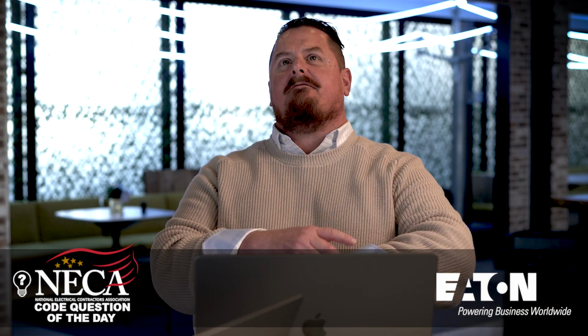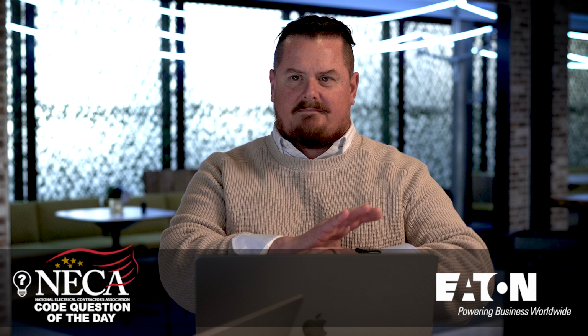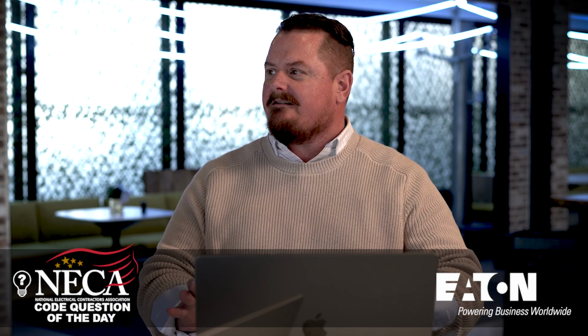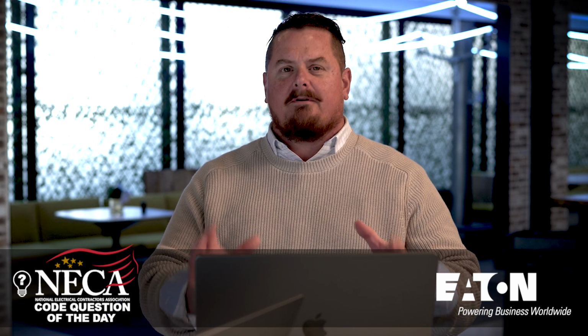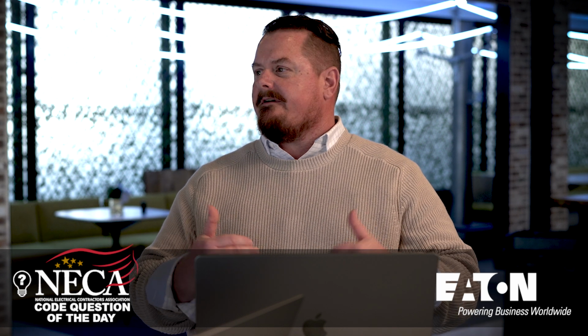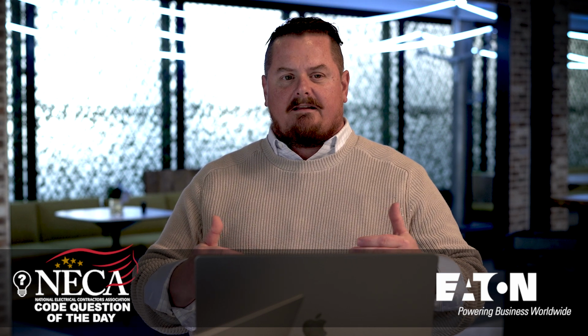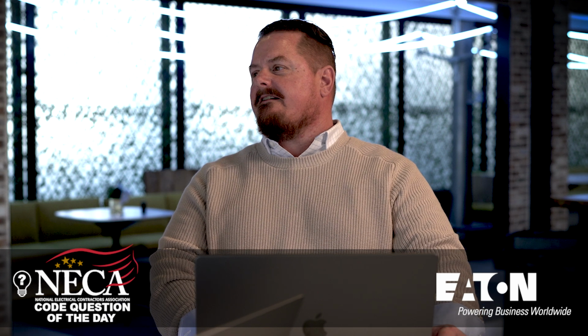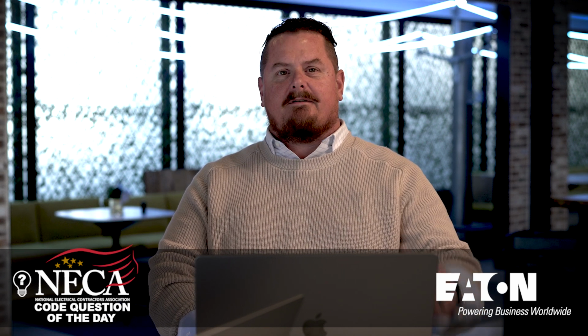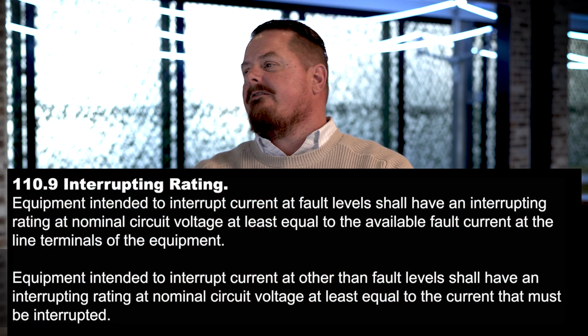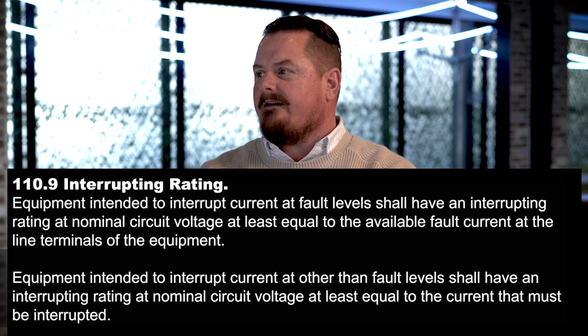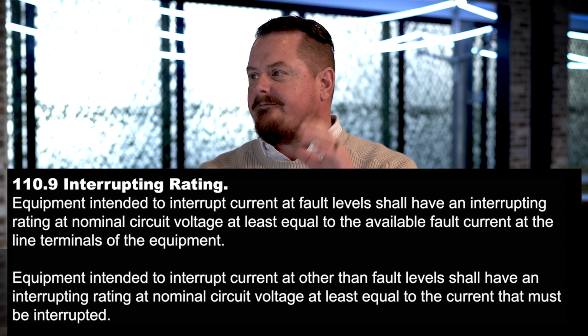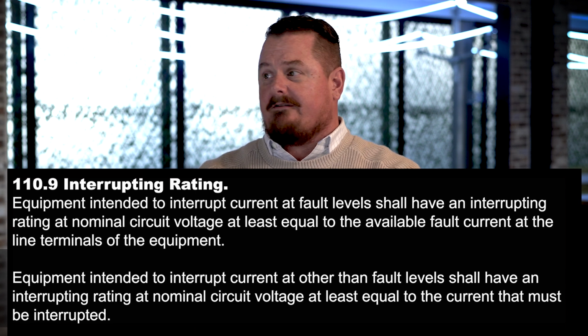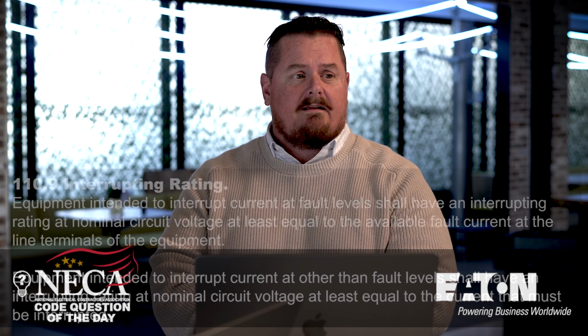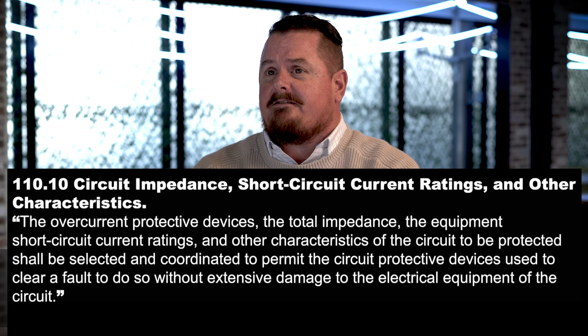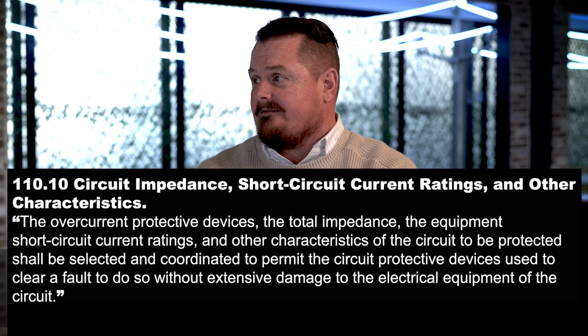If we strip it down to the most basic concept, where all of our requirements start for interrupting rating and short circuit current rating is sections 110.9 and 110.10, general requirements, right? 110.9 tells us we have to use properly rated overcurrent protection devices for the specific available fault current with the proper interrupting rating. And then 110.10 says our equipment has to be short circuit current rated for what it's going to be exposed to.